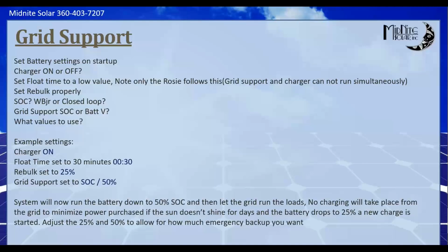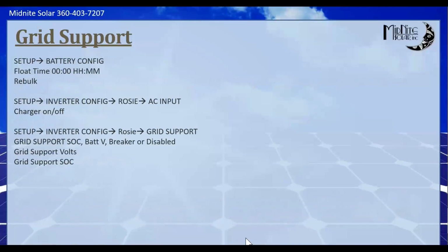And then if you connect back to the grid, say at midnight, you've drained your battery down to 50%, and then there's no renewables for the next couple days, and the parasitic loads draw down on that battery until it's 25%, then we'll start a new charge. We'll do a complete charge, and then we'll go back into grid support again. So that's kind of the meat and potatoes of grid support. It's an elegant solution, but as I said, it does prioritize the charger over the grid curtailment. So that's something to keep in mind.